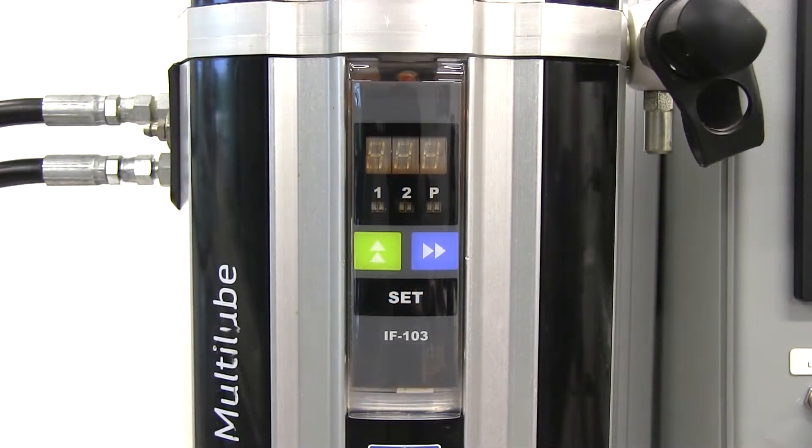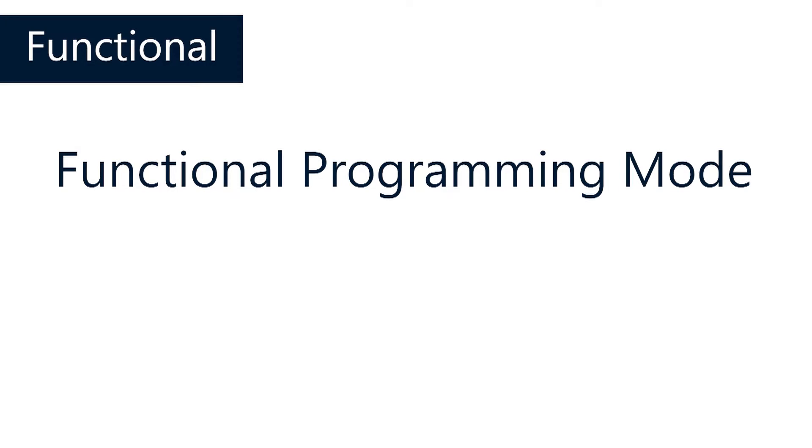The functional mode is displayed very quickly when the control unit is powered on. If 1 2 P is indicated, then all is good. No change is required. Otherwise, the mode must be changed via the functional programming mode accessed with password 222.